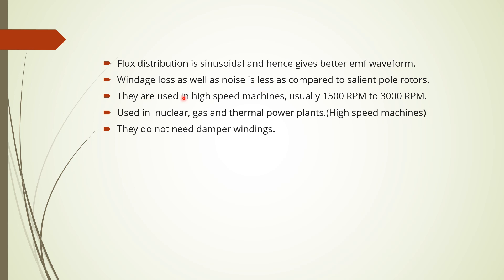Non-salient pole machines operate at high speeds, normally from above 1500 rpm up to 3000 rpm, compared to salient pole machines which operate below 1500 rpm. They are mainly used in nuclear power plants, gas power plants, and thermal power plants. These machines are generally known as turbo alternators. The flux distribution is uniform, so they give a better EMF waveform, with lower losses and less noise. They do not need damper windings because the oscillations during changing load conditions are automatically damped out by the windings.